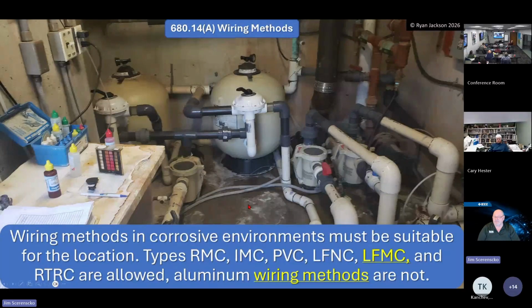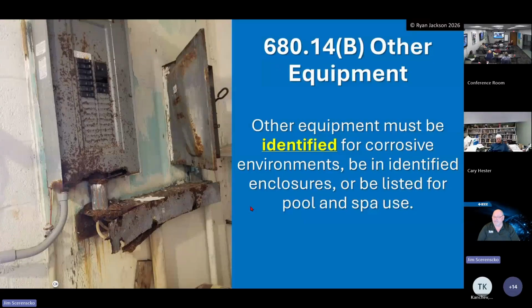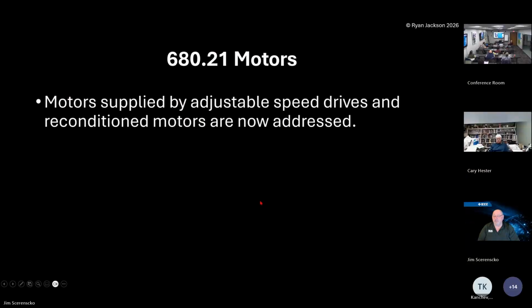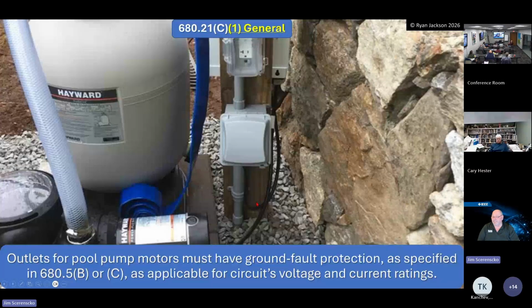The only thing we can do is write a notice to the owner of violation, and it usually looks like this. And I'm not kidding. I mean, it's bad. And a lot of times they just turn a blind eye to it. As long as the outside has a couple of palm trees around it and some chairs and stuff, no one looks in those rooms, but those rooms are bad. That chlorine just eats through this stuff. Motors, same way. We want to make sure the motor is listed for pool equipment.